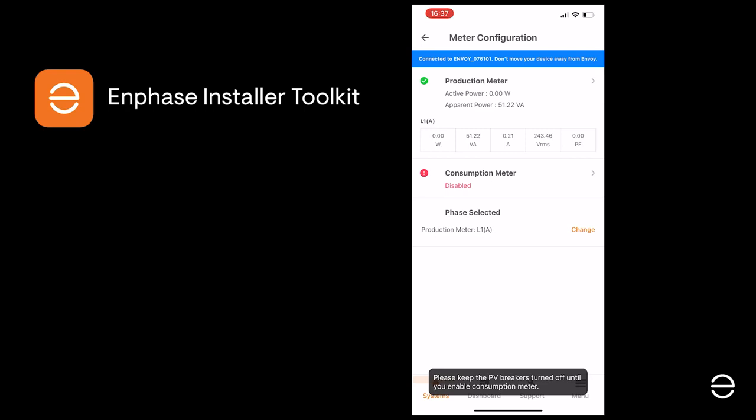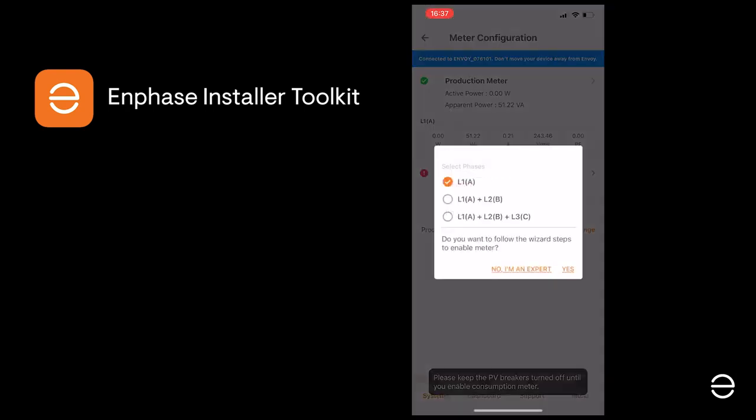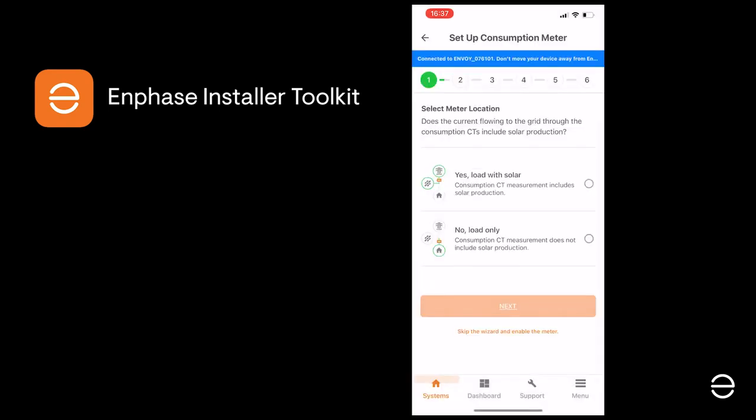You can now configure the consumption meter and as before specify the phase type. You then need to select whether you want to measure consumption with or without solar, depending on where you have placed the CTs. In the vast majority of cases, this will be between the PV system and the breaker box.